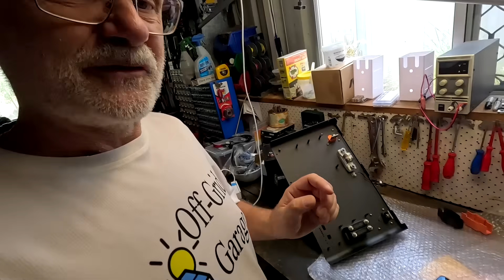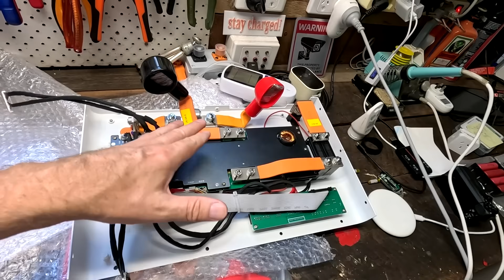Even though I must say the trip amps is 270 amps. So in theory, if the BMS doesn't trip at 200 amps at the latest, you could end up with 270 amps flowing through your battery, a faulty BMS potentially, and all these bus bars and connections. They need to withstand 270 amps at least. Are these bus bars rated for 270 amps?